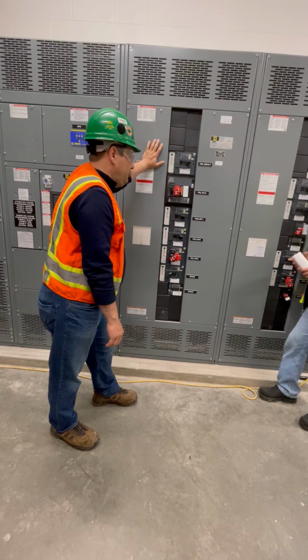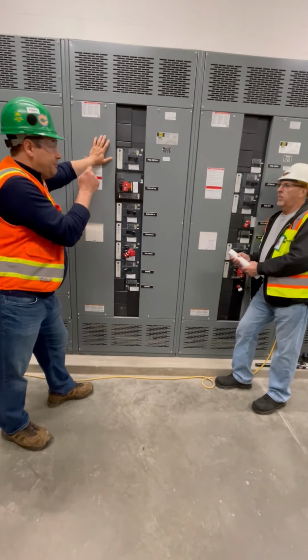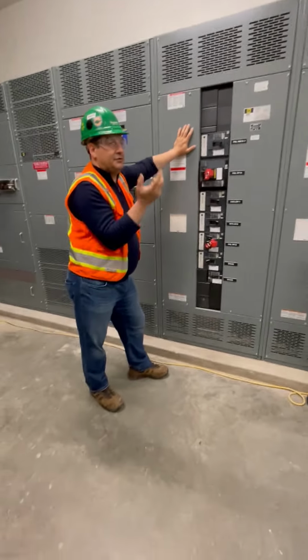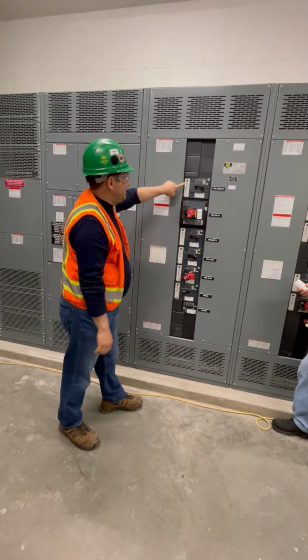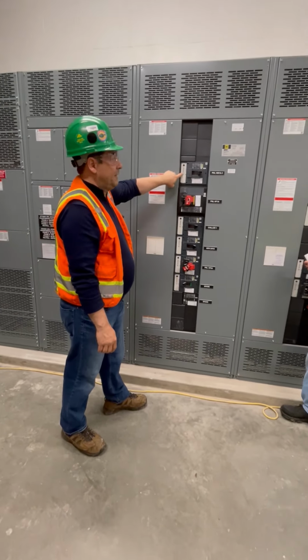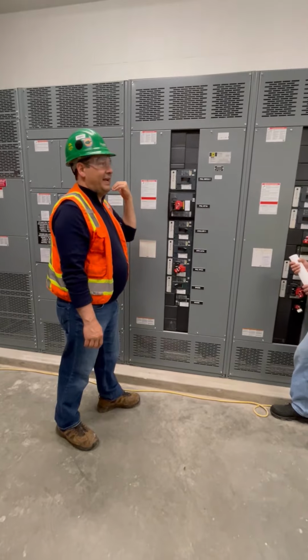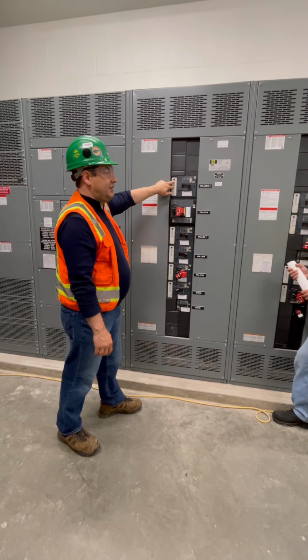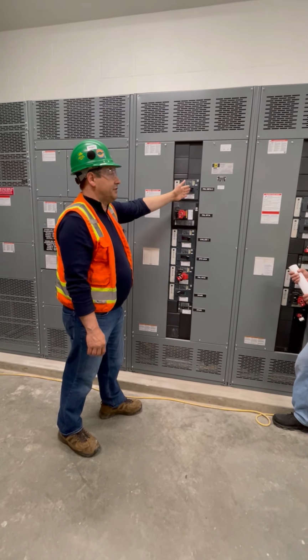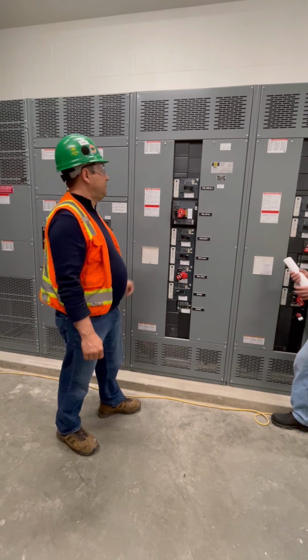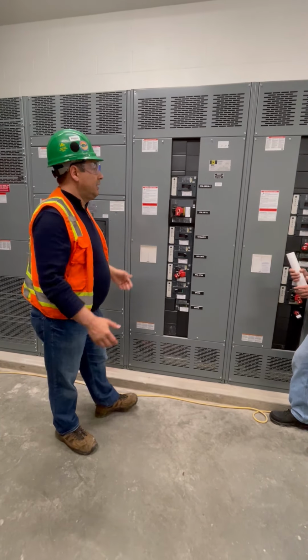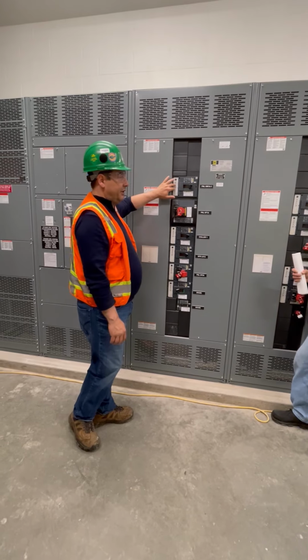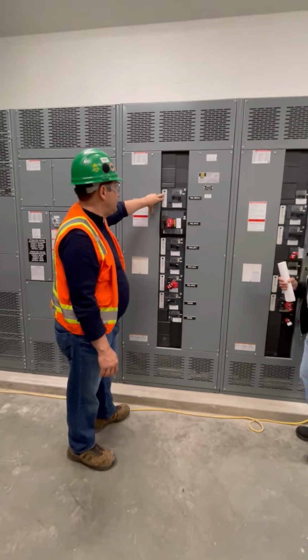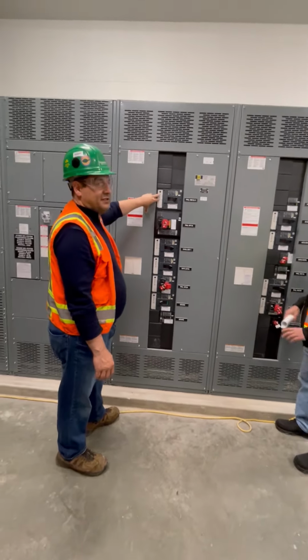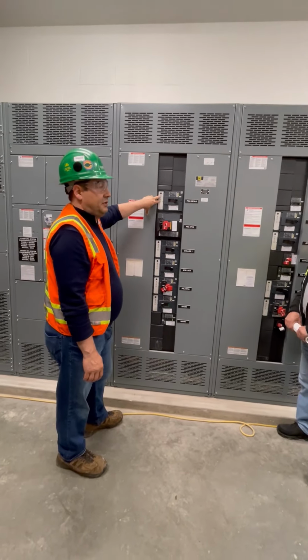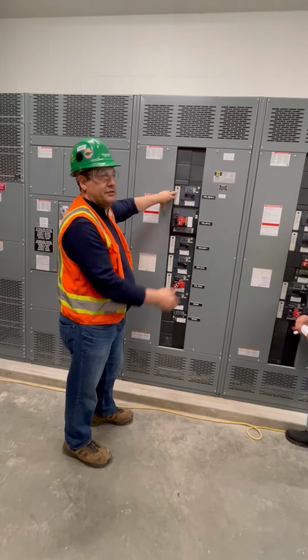Now, when you do maintenance, is it good to always do a trip by push to test? Absolutely. But at the same time, when you do maintenance, when they test this breaker, they'll also trip the breaker mechanically with the trip unit, with the test set, in order to validate the same function, right? Oh, yeah. So that push to test is hardly used, because you can check that function when you test the breaker. On these test sets, you can say test the breaker without tripping or test the breaker with tripping. We always test it with tripping to check that mechanical function. Sure.